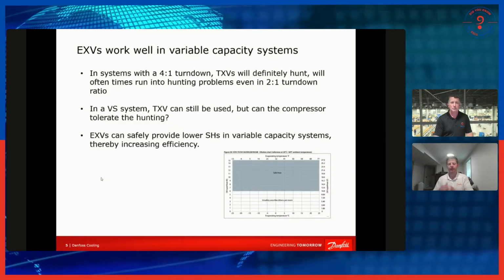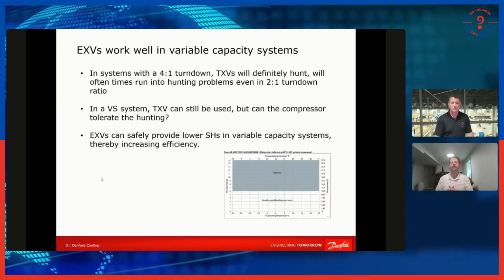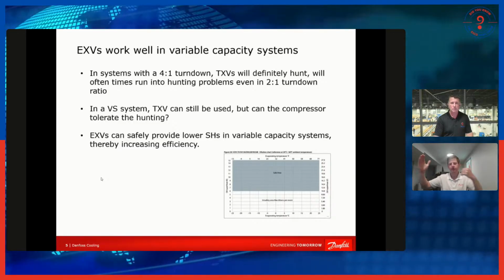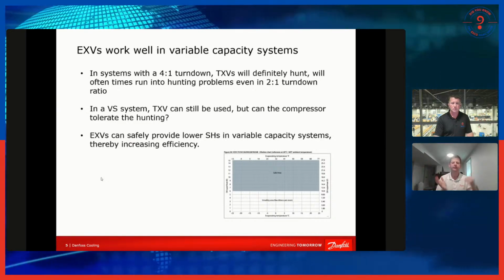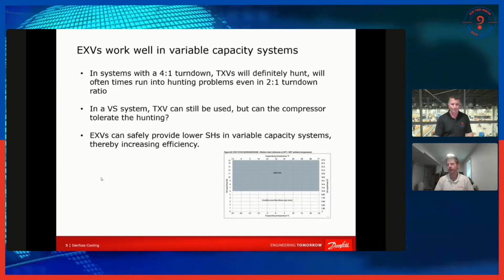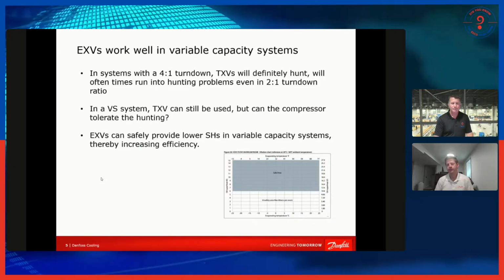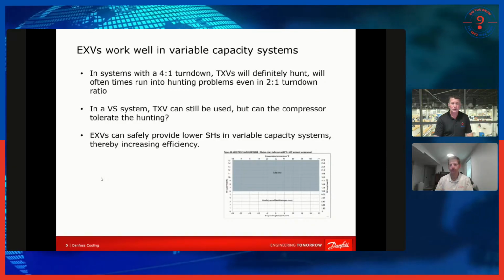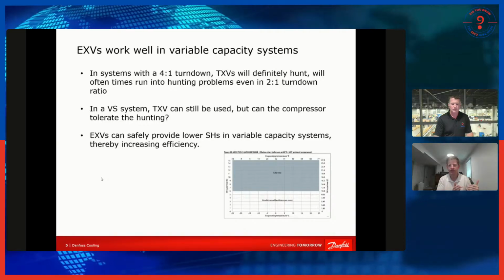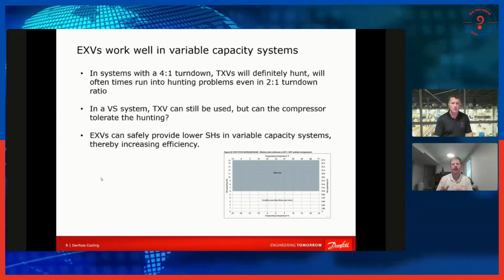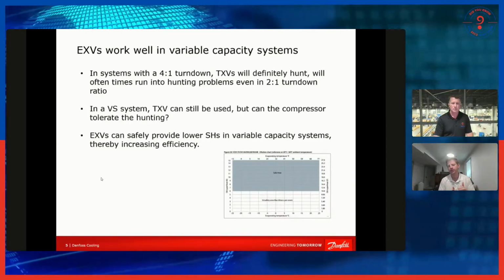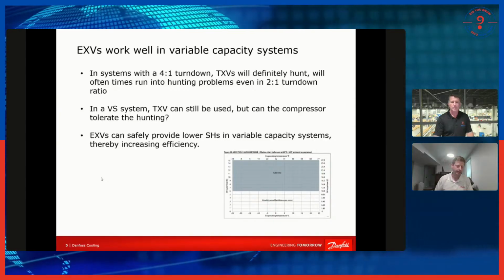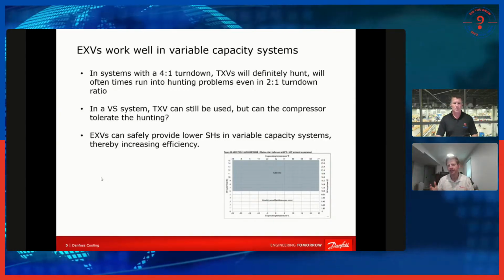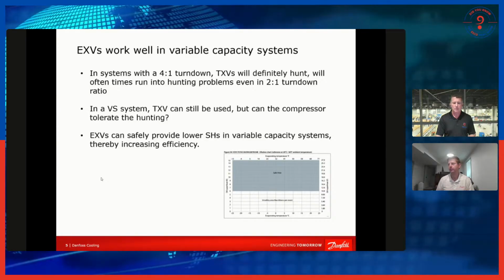If you've got a system that's got a 4-to-1 turn down ratio, so a compressor that can run up at 6,000 RPMs versus 1,500 RPMs, your TXV is going to be hunting by the time you get down to 1,500 RPMs. Even sometimes if you just have a 2-to-1 turn down ratio, you go from 3,600 RPMs to 1,800 RPMs, even there, sometimes the TXVs can start to be hunting as it starts to get to the low end. So that's one thing where if you use an EXV, you don't have to deal with that hunting problem.